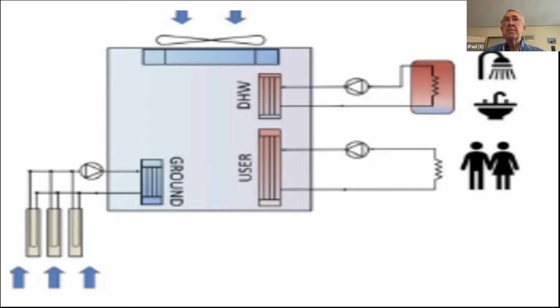What you have on the screen now is kind of a blurry example of what would be called a multi-source heat pump. This is an extension of what people usually have outside of their home right now, which is a central air conditioner box. Instead of only being a central air conditioner for cooling, a heat pump has what's called a reversing valve internally so that it can be a heater or a cooler, whichever you need at the time. In this case, it's a multi-source heat pump. It's got an air source element at the top, with a fan and a coil with refrigerant in it. That is an air to refrigerant heat exchanger, and that's the basic element of anybody's outdoor condenser box for a central air conditioner.